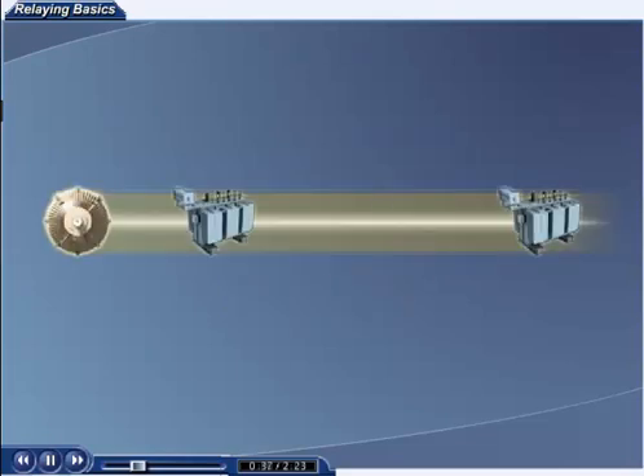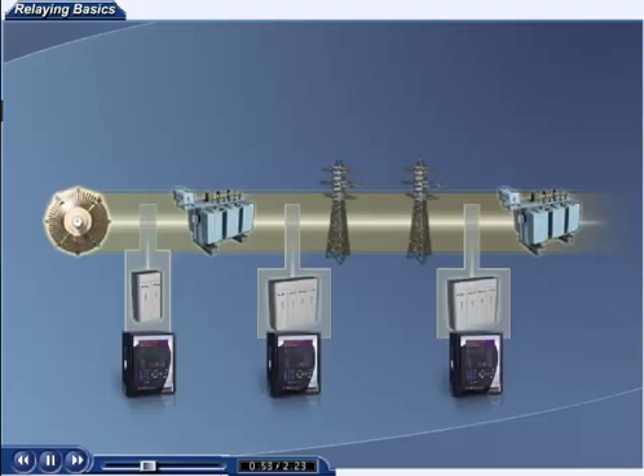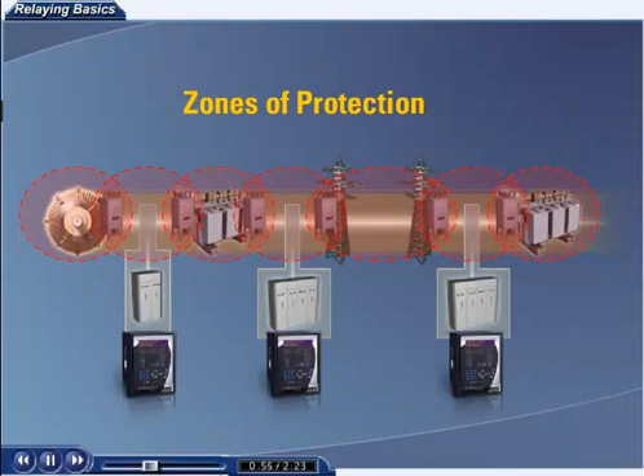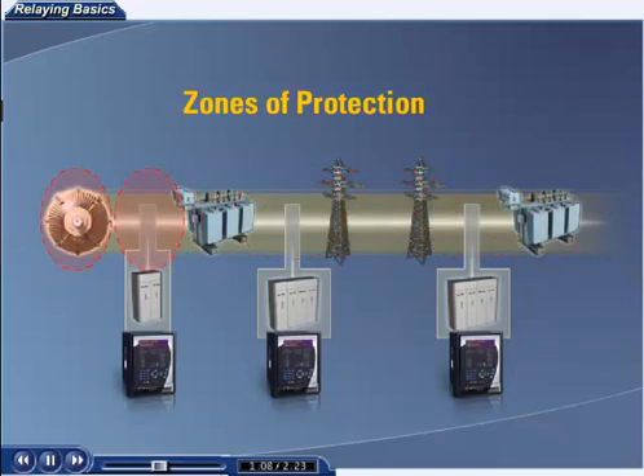Circuit breakers are located between each power system component, which makes it possible to isolate and disconnect the faulty component. If a breaker isn't installed between two adjacent components, both components will need to be disconnected for a failure in either one. One of the protection engineer's most powerful tools is the concept of zones of protection. The boundary of a protective zone represents the region that a particular protective element covers. It is necessary for these zones to overlap to ensure proper protection. If two zones did not overlap and a fault occurred at the boundaries of these zones, it is possible that no relays would be tripped.